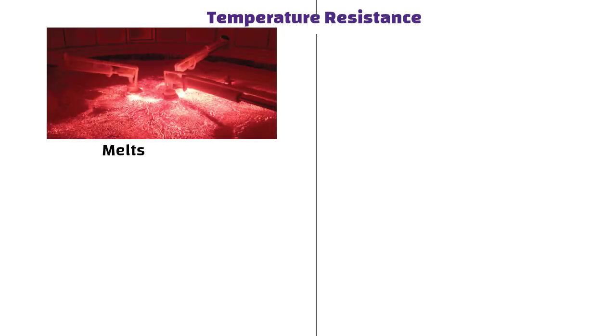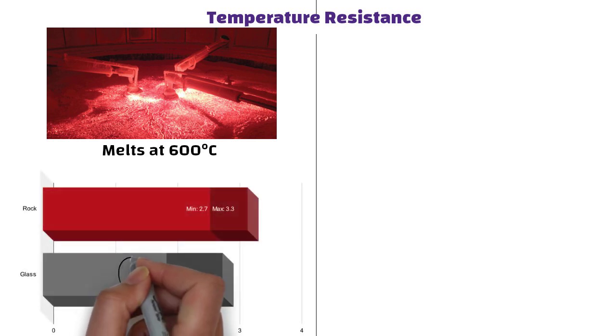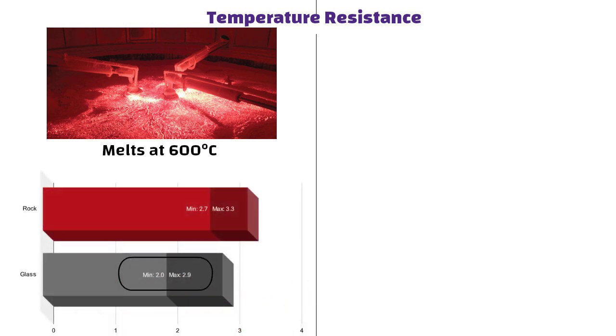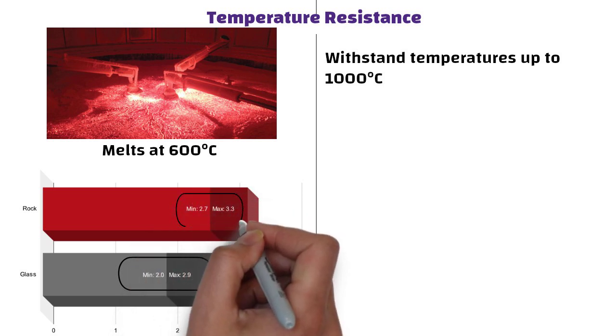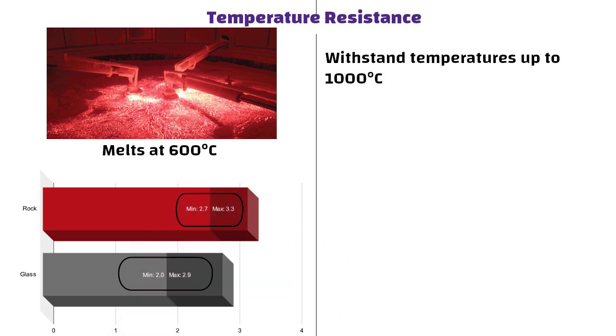Temperature Resistance: Glass wool melts at around 600 degrees Celsius and has an R-value of 2 to 2.9 per inch. Whereas rock wool can withstand temperatures up to 1000 degrees Celsius and boasts an R-value of 2.7 to 3.3 per inch, making it slightly better at insulation than fiberglass.